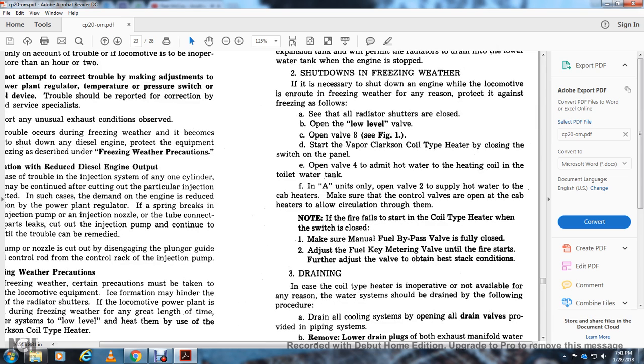Note: if the fire fails to start in the coil type heater when the switch is closed, make sure the manual fuel bypass valve is fully closed. Adjust the fuel metering valve until the fire starts. Further adjust the valve to obtain the best stack conditions.